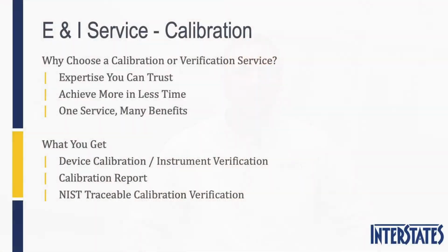Some of the common services I see out there are instrumentation calibrations, where each device is pumped up or heated up, or flow is run through a device on a periodic basis, and the results from that calibration are then documented in a sheet and turned over to the facility in the end. That way the facility has a means to know that this device was calibrated on this date, it was working properly, it was accurate, or maybe on the other hand, this device needed replacement. Its electronics were fried, its calibration was off and unable to be adjusted. That's one of the E&I services that's out there.